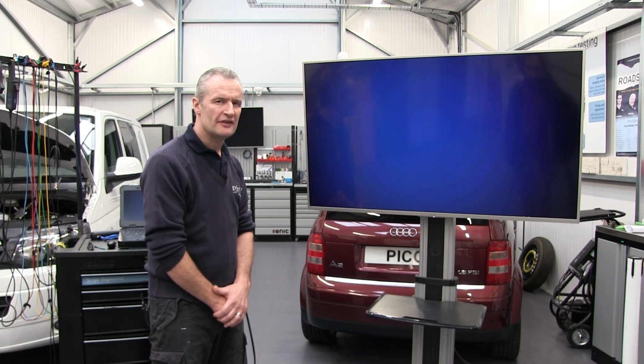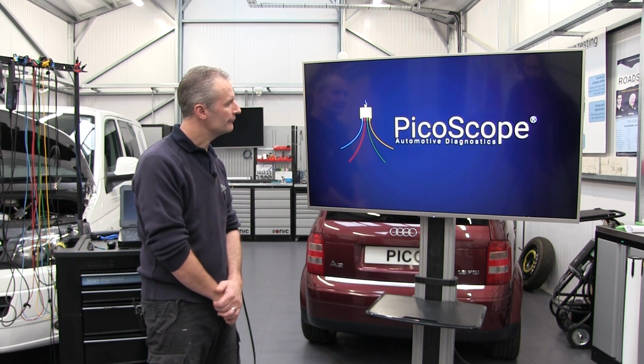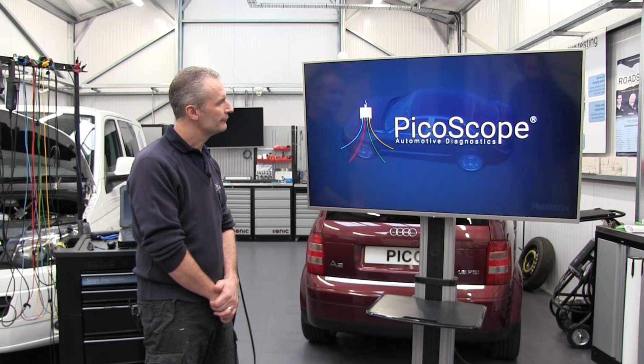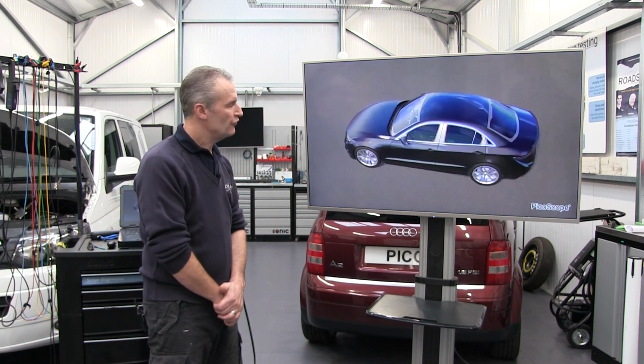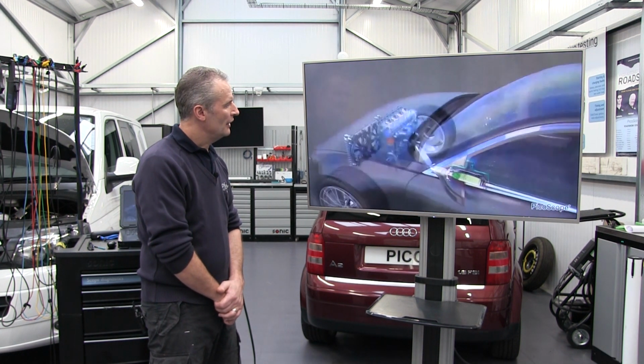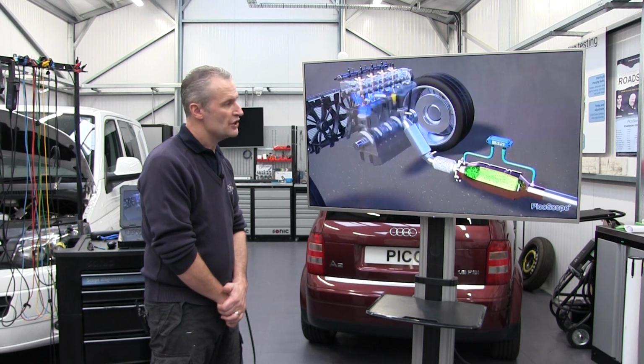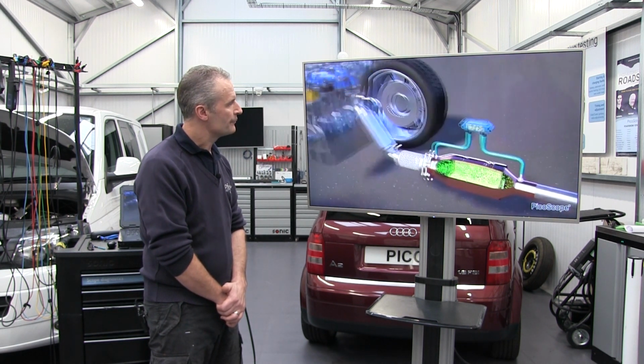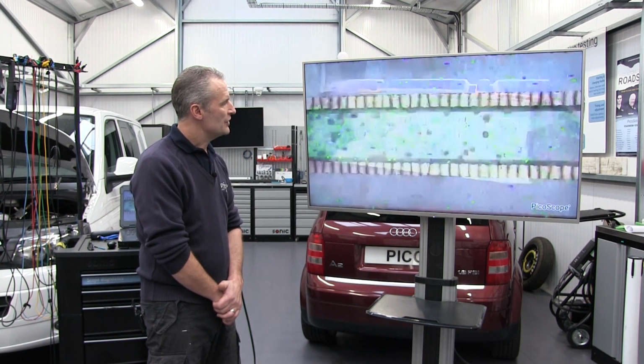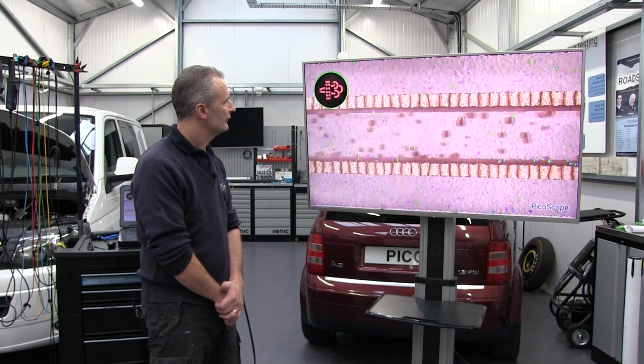WPS500 pressure transducer, now looking at DPF back pressure. Let's have a look at the animation and see how we apply the transducer in this scenario. So here we have a 4-cylinder diesel and we're looking at differential DPF pressure. And we can see there that the pressure is starting to build.